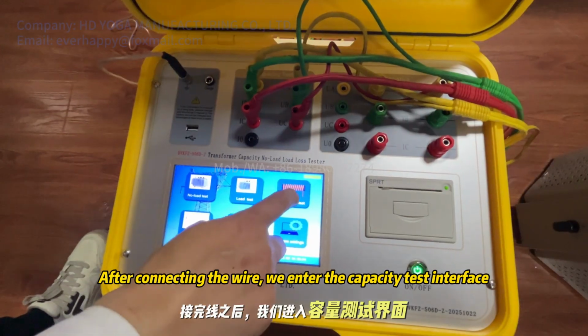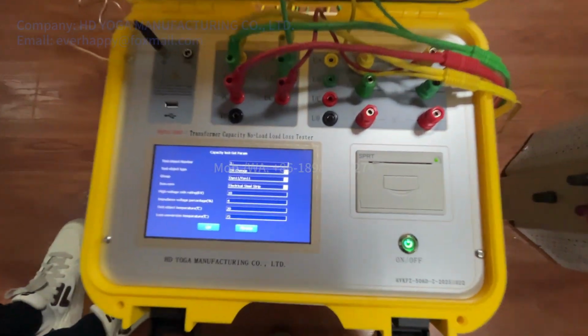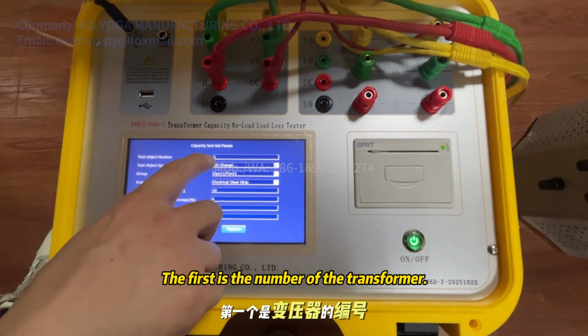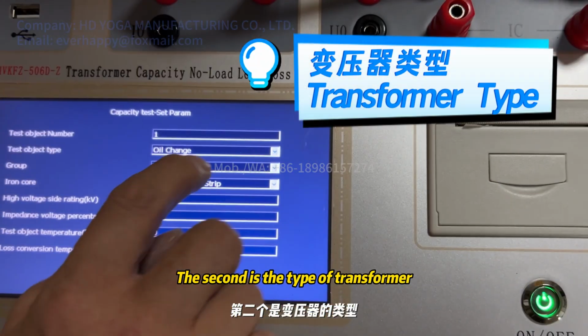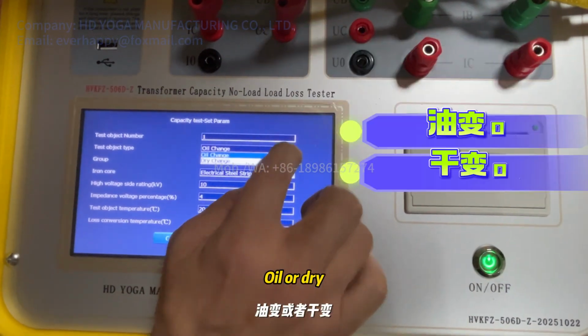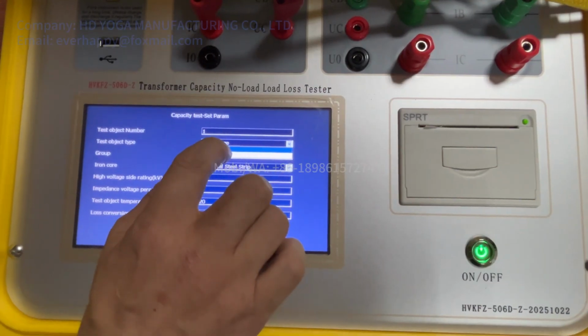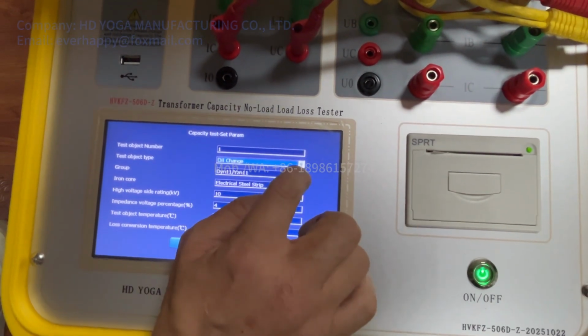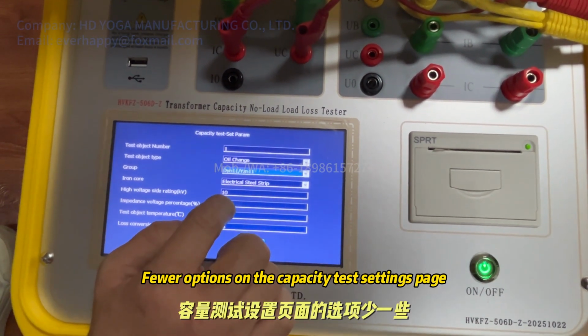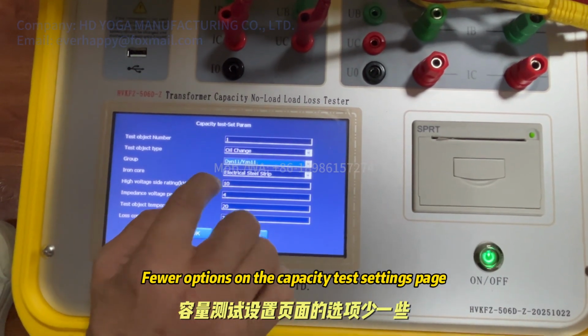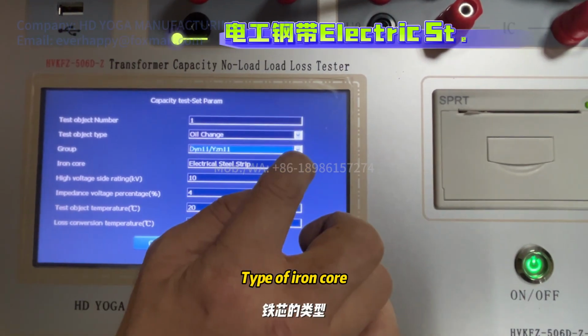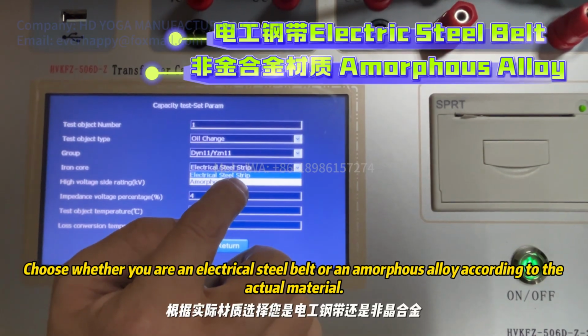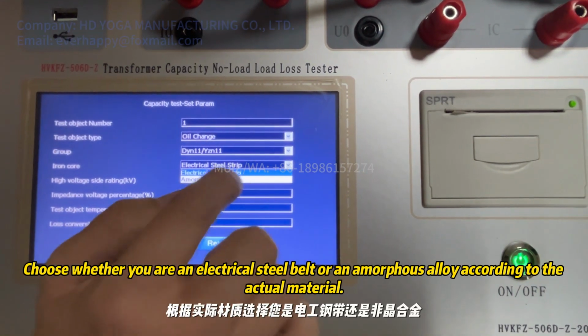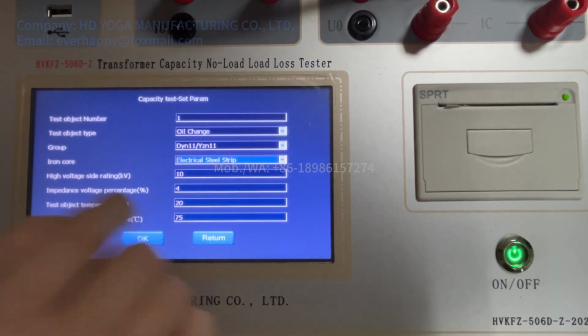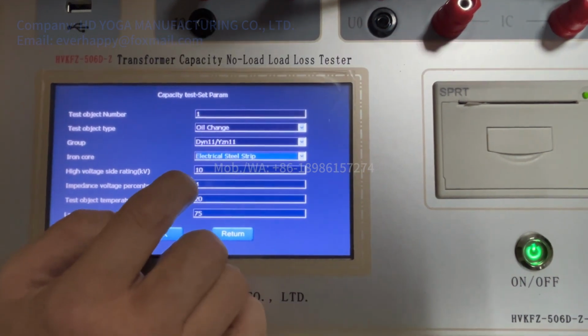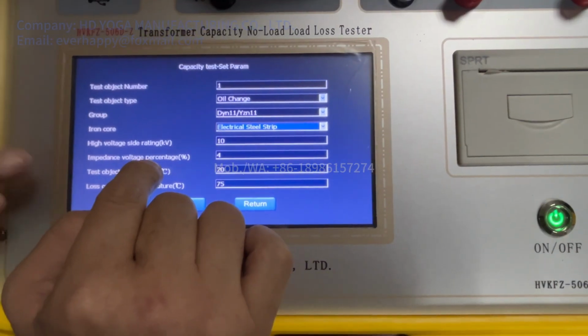After connecting the wire, we enter the capacity test interface. Same here. The first is the number of the transformer. The second is the type of transformer, oil or dry. We choose accordingly. The same goes for the third one, winding connection. Fewer options on the capacity test settings page. Type of iron core. Choose whether you are an electrical steel belt or an amorphous alloy according to the actual material. Rated voltage on the high voltage side. Fill in according to nameplate.